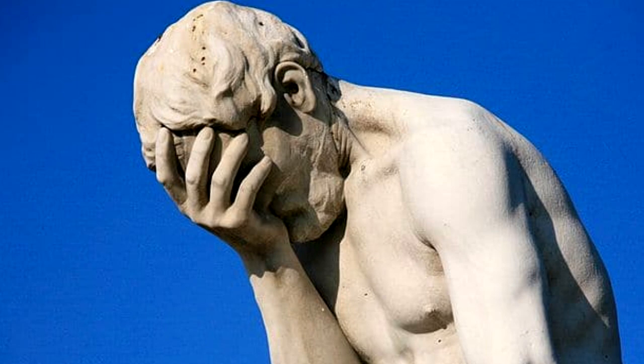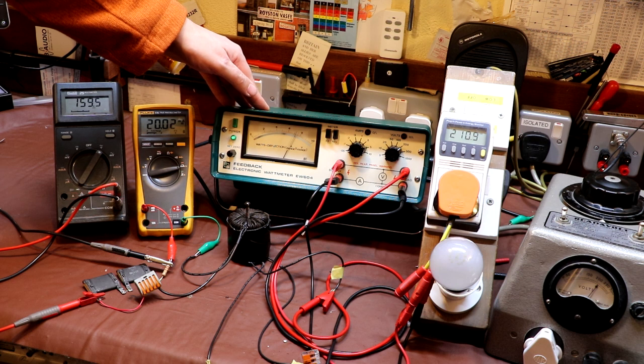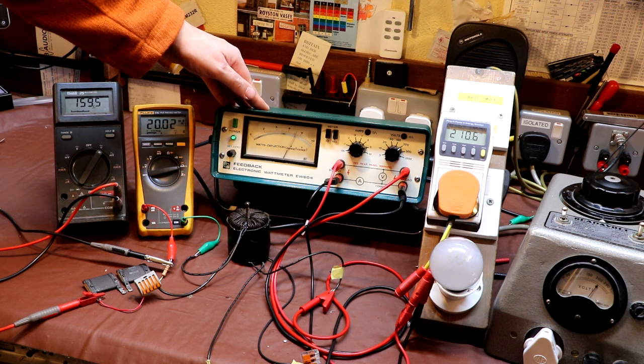So having thoroughly mangled up probably a large number of scientific principles there, I think it's time to actually get back to the workbench and let's see if we can just measure the overall efficiency of our transformer, and then maybe just see if we can split it into the iron losses and the copper losses. Now I'm afraid previously when I measured the iron loss of our transformer I maybe got a little bit ahead of myself, so I've decided just to take a step back.